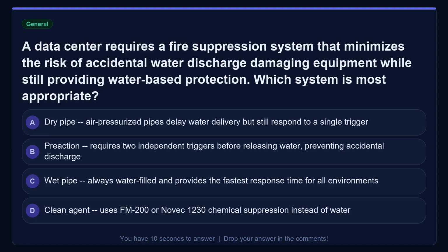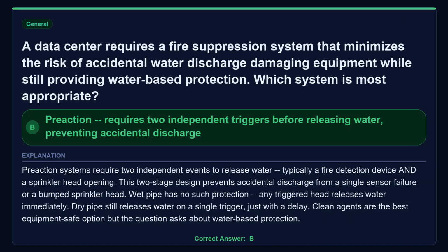A data center requires a fire suppression system that minimizes the risk of accidental water discharge damaging equipment while still providing water-based protection. Which system is most appropriate? The correct answer is B. Preaction requires two independent triggers before releasing water, preventing accidental discharge.